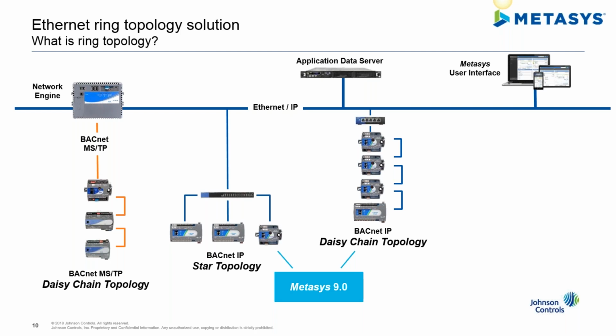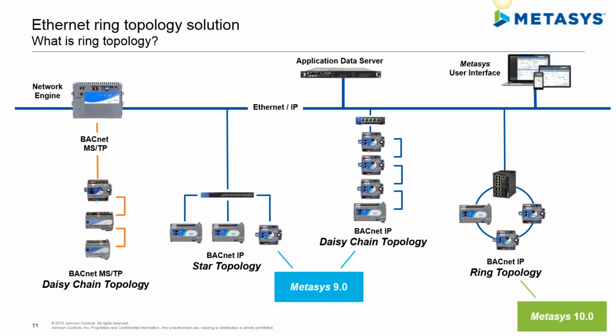The problem with daisy chaining is that it's not as resilient to a cable failure or an offline controller as the star topology. If a controller went offline or if a cable were to break, the communication between the engine and that failed node and all the downstream nodes would fail as well, and communication would be lost. So we've addressed that in Release 10 by offering a third topology option, which is the ring topology.